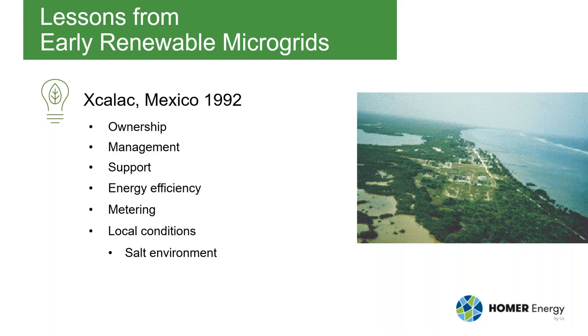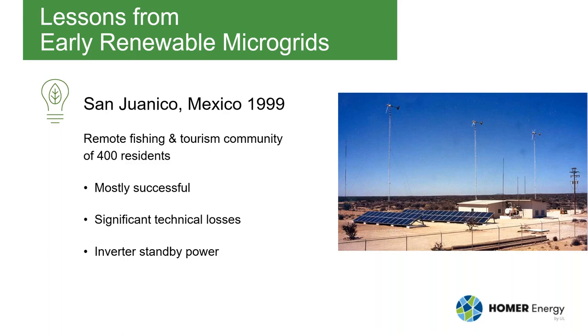Another lesson was the importance of energy efficiency. We put in this system and the villagers all went out and bought secondhand refrigerators — really inefficient compared to new modern ones — which overwhelmed the system. It's much more cost-effective to spend money on energy-efficient appliances than to power inefficient ones. There was also no metering, so people didn't care about efficiency. And local conditions matter — this was a salty ocean environment with corrosion problems.